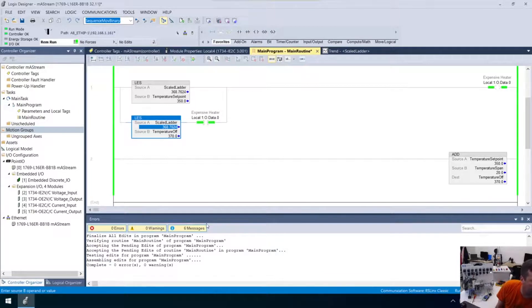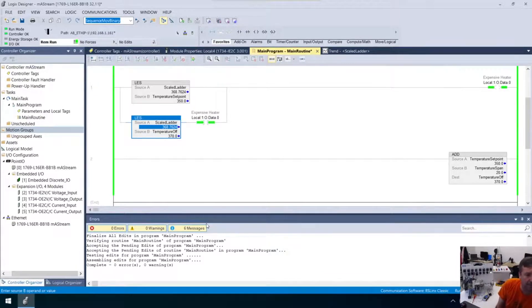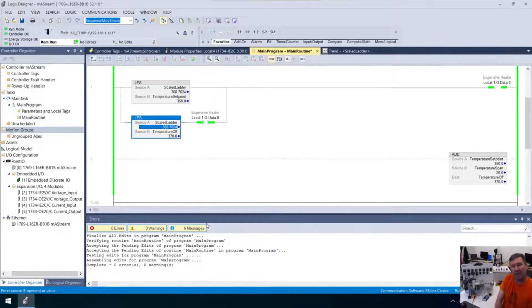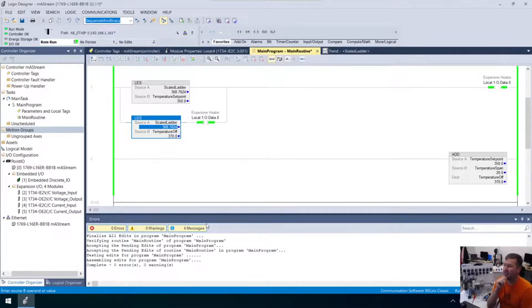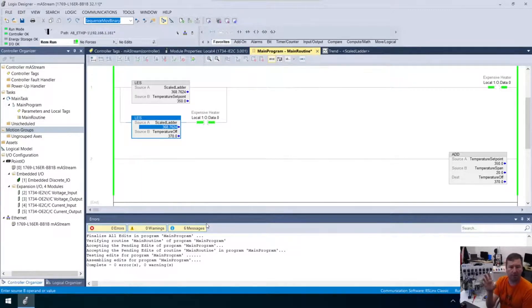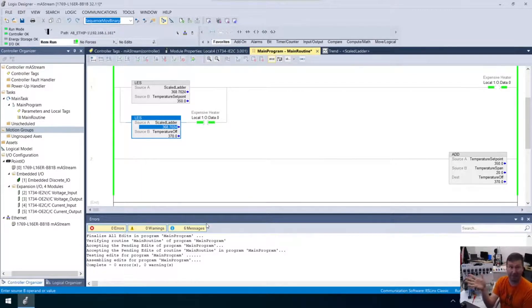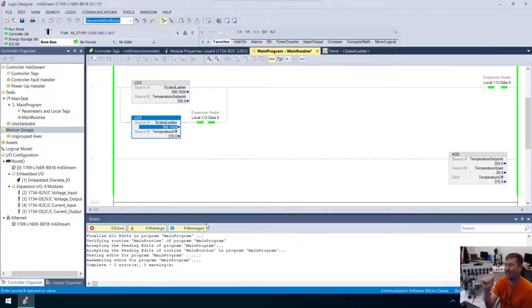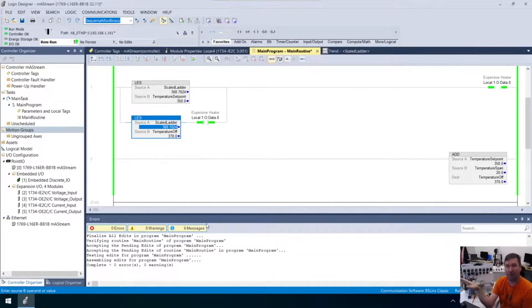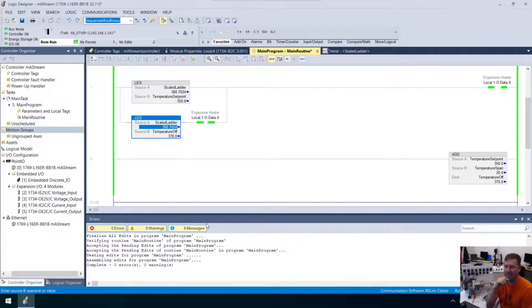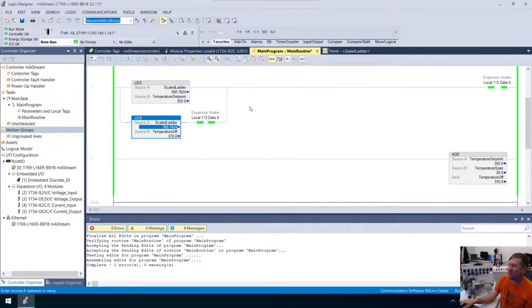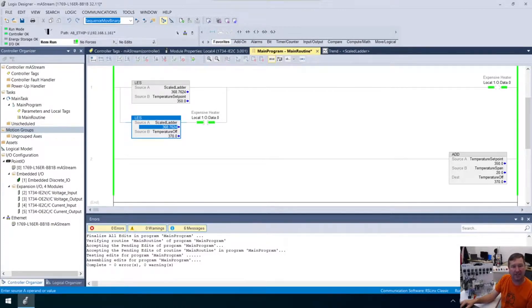So our heater is running. It's going to start raising our temperature. And we're going to get, there's 350. There's 356. We're still running. Now note at this point though, 356 is greater than this temperature set point. This is false. This one is true. And we're going to pump this on up. And there you go. When we hit 375, heater goes off. Now that's going to coast back down, 349. And it's going to go back up and back down. Lastly, John, PID is good if there is a delay between the input and output, especially when things can overshoot like temperature. Yeah. And you know, so you can have, we'll call it a pulsed output and you can actually have a solid state relay that's kicking on a heater. That's not that uncommon, as opposed to a four to 20 signal. So I should add that to the PID series. All right. So that covers the heater that covers chilling.